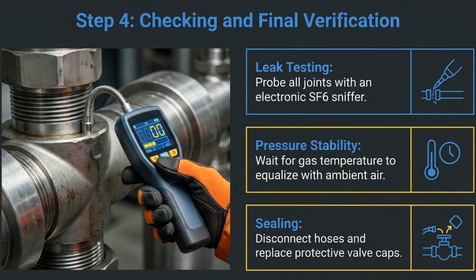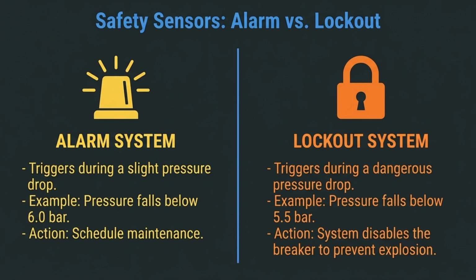Step 4 is checking and final verification. Perform leak testing on all joints with an electronic SF6 sniffer. Ensure pressure stability by allowing gas temperature to equalize, then seal the equipment. Safety sensors include alarm and lockout systems. An alarm triggers during a slight pressure drop, requiring scheduled maintenance. A lockout triggers during a dangerous drop, disabling the breaker to prevent explosion.